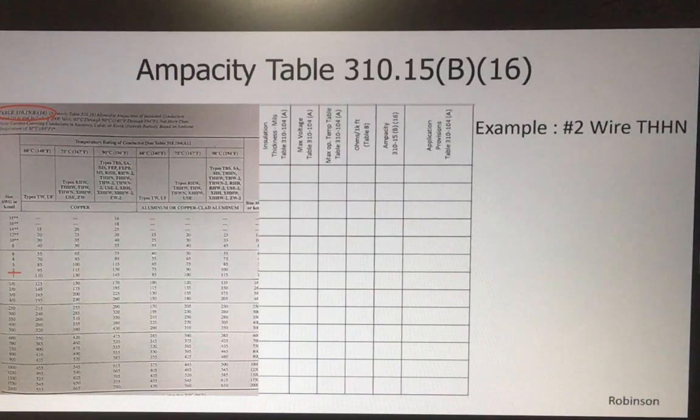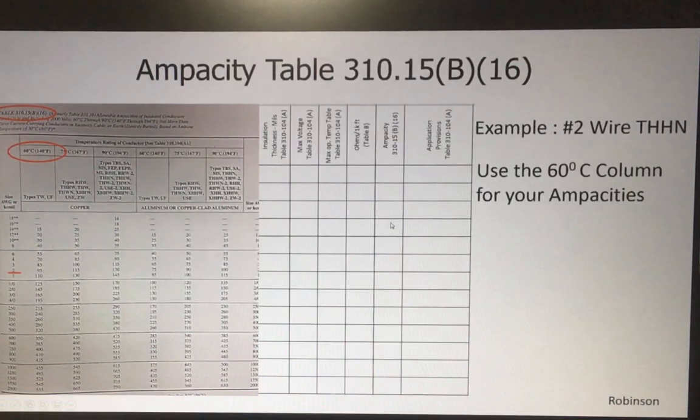And the whole thing is like I said with the chain, everything on the circuit has to be rated for 90 degree. And there's no such thing as a 90-degree circuit breaker. The biggest circuit breaker out there, highest rating is 75. So there's some locations where it uses the 75-degree column, but for purposes of this exercise and project, just use the 60-degree column for all your ampacities.